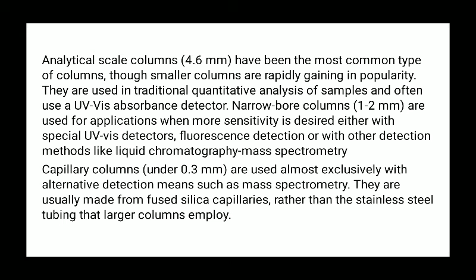Analytical scale columns have been the most common type of column, though smaller columns are rapidly gaining in popularity. They are used in traditional quantitative analysis of samples and often use a UV absorbance detector. Narrower bore columns are used for applications when more sensitivity is desired, either with a special UV detector, fluorescence detector, or with other detection methods like liquid chromatography mass spectrometry. Capillary columns are used almost exclusively with alternative detection means such as mass spectrometry. They are usually made from fused silica capillary rather than the stainless steel tubing that larger columns employ.